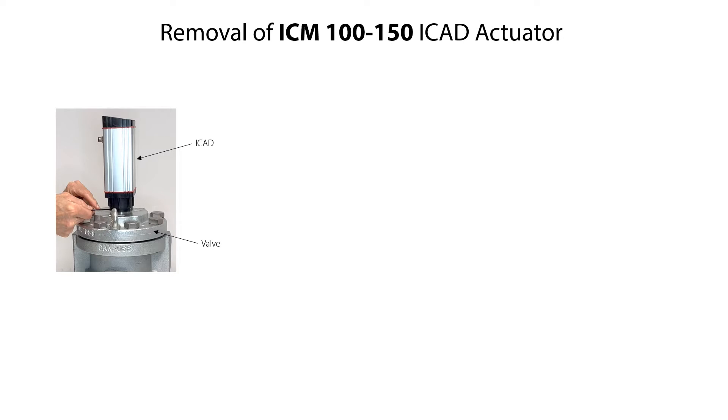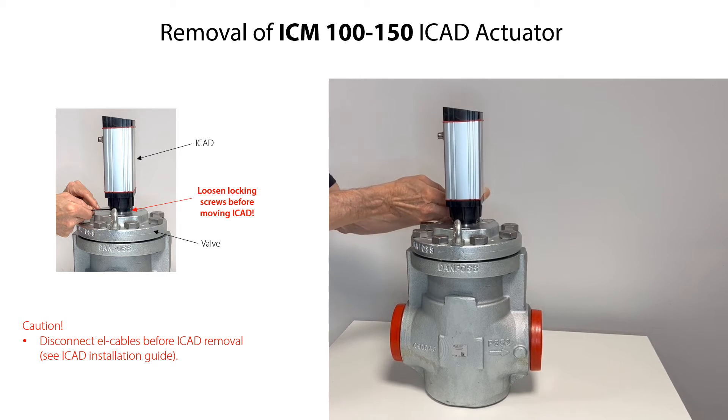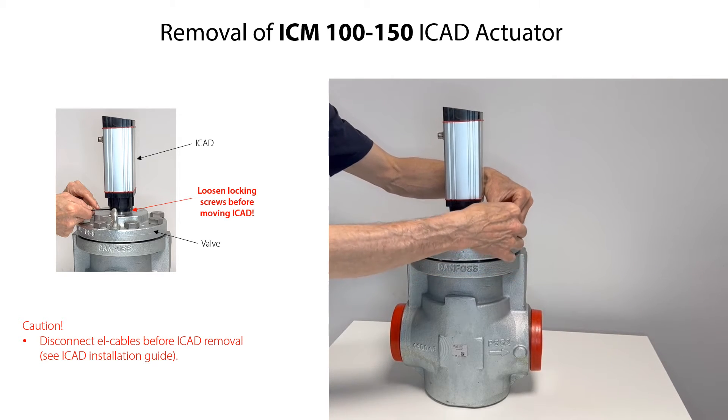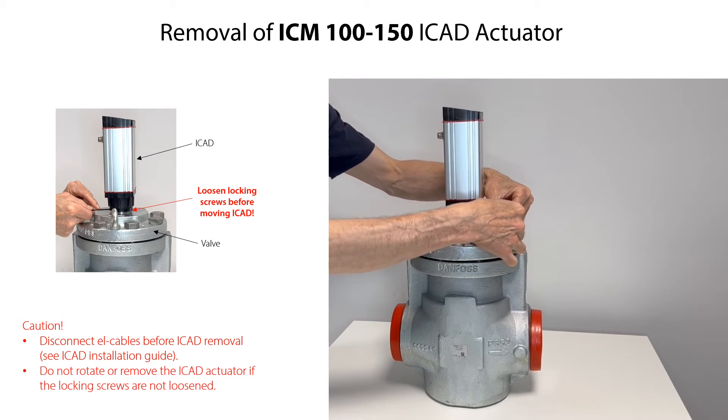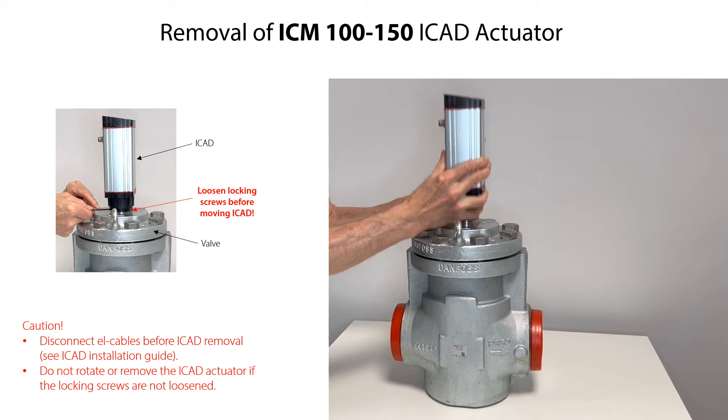To remove the ICAD actuator from the valve, first remove the electrical cables from the ICAD according to the instructions given in the ICAD installation guide. Then loosen the locking screws so that they are not in contact with the valve top. Finally, carefully remove the ICAD actuator from the valve. Do not rotate or remove the ICAD actuator if the locking screws are not loosened.